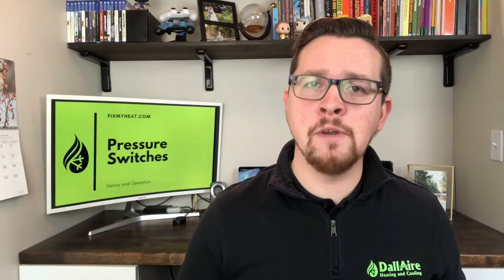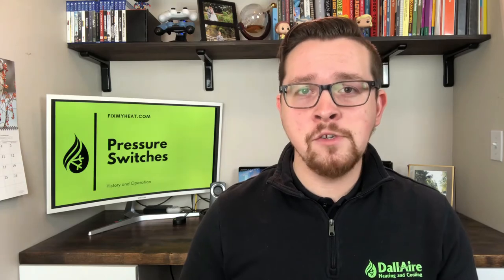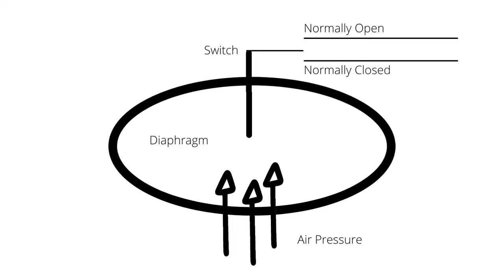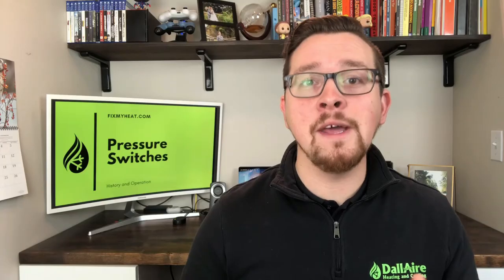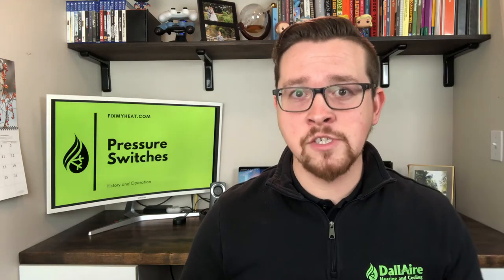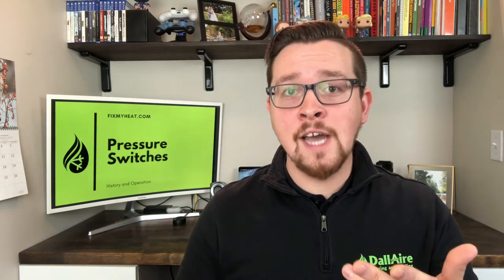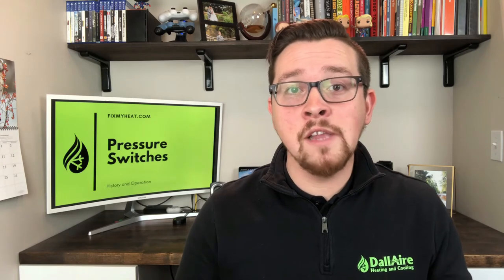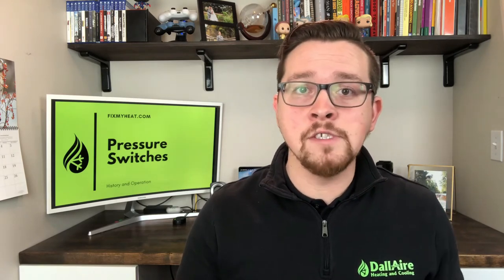The most common type of air pressure switch relies on the air movement through that tubing to either pull or push on a bladder inside of a plastic housing, or if it's an older furnace, a metal housing. That bladder, as it moves up or down according to that pressure, actuates an electric switch. It will either open or close the contacts of that switch at the rated pressure. Some switches have normally open and normally closed contacts. Some have just one or the other. So aside from the pressure switch rating, make sure you've got the correct contacts on the replacement pressure switch. If the bladder tears, the housing cracks, or the electrical switch inside fails, it won't allow the furnace to operate anymore because it won't be able to monitor the exhaust pressure.